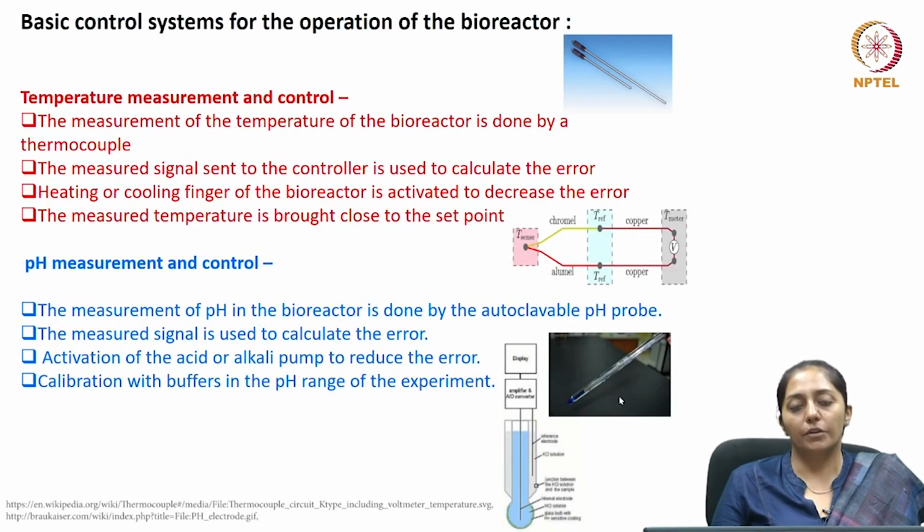Then talking about the control systems present inside the reactor. For temperature control and measurement, generally we have a temperature probe. This probe is based on the principle of a thermocouple. The temperature of the reactor is measured by this probe, and the measured signal is sent to the biocontroller, which is used to calculate the error.